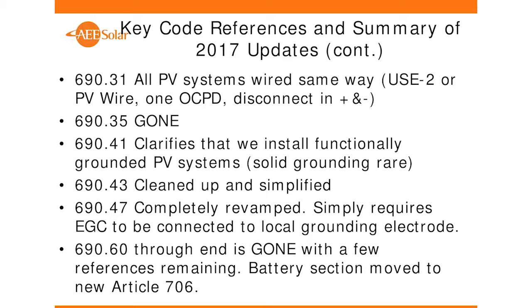31, basically, and this is an important issue, I think, and several folks have brought up questions about this over the last couple of days: in the 2017 code, we want everything wired the same way. So there's not this, in 2014 and before, we have ungrounded systems, we have grounded systems. And ungrounded systems require fusing, positive and negative, require PV wire, multi-conductor cable, all this stuff. And we had to worry about all that, make sure your modules have PV wire on them and all that kind of stuff. And with an ungrounded system, because an ungrounded system is a less safe system, and we're worried about Class 2 European wiring systems, all these kind of things were flowing around related to that.